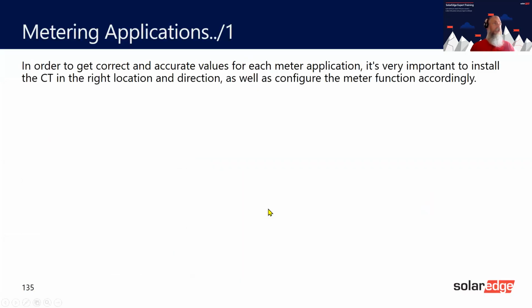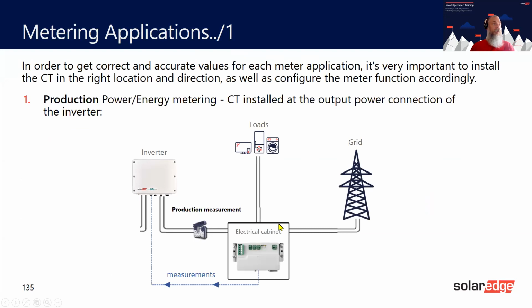So let's get this slide up. Here we go. So in your electrical cabinet or in your enclosure or wherever you wish to have this, if you were doing production, it would have to be in line before any of the loads, before the grid, and the CT would be here, which it is, and you would basically measure what the inverter is producing.